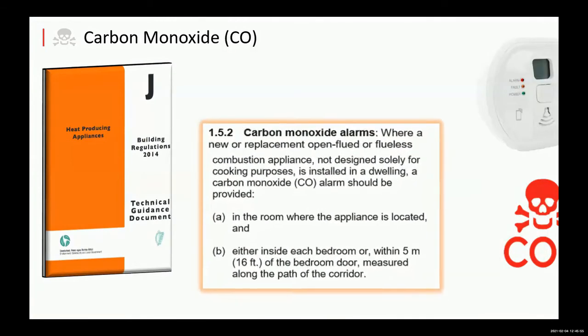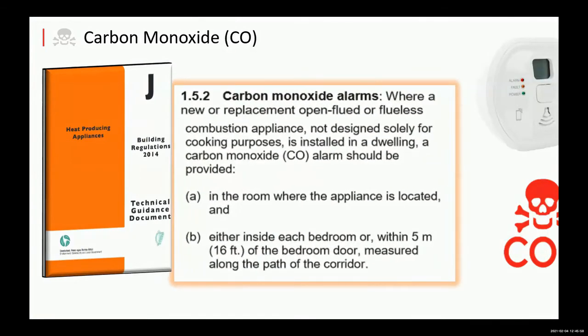Again, we have to delve into the document to see exactly what they're talking about here. So where a new or replacement open flued or flueless combustion appliance not designed solely for cooking purposes is installed in a dwelling, a carbon monoxide alarm should be provided, A, in the room where the appliance is located, and B, you get an option here, either inside each bedroom or within 5 meters, that's 16 feet in old money, of a bedroom door measured along the path of the corridor. And that's important from that point of view. So there's 2 locations. If you have just one heating source within the house, you have 2 alarms. If you have 2 heating sources within the house, you have 3 alarms, and so on and so forth. And one has to be in the location of the appliance, and the other has to be within 5 meters of any bedroom.